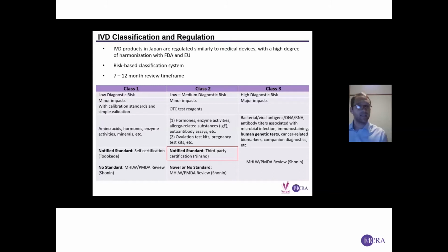When you're talking about sample size, the sample size is going to vary significantly depending on the purpose of that clinical data. And so if you're just looking to compare to a predicate product, typically a sample size of around 100 subjects is required. For a novel product where you're using the clinical data to evaluate the safety and effectiveness of the product, irrespective of predicates, it's going to be more like 200 to 500 subjects. And then for limited indications, like an orphan indication, the requirement for clinical data is going to be much lower.